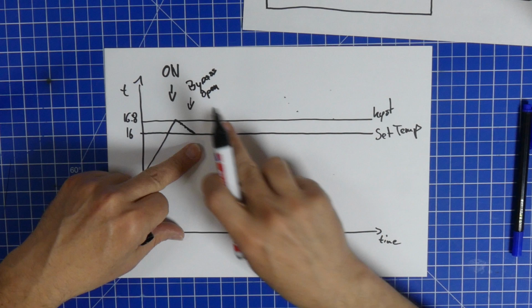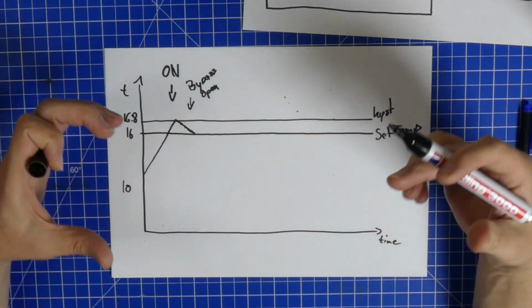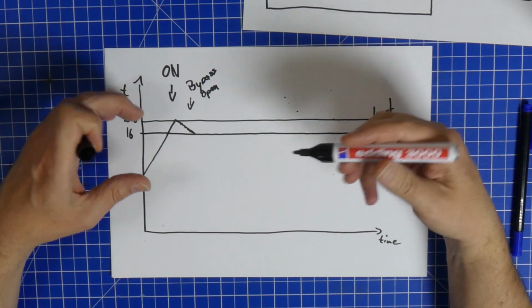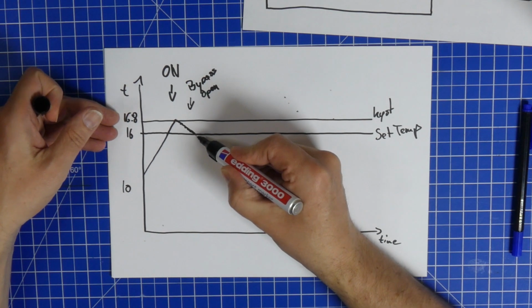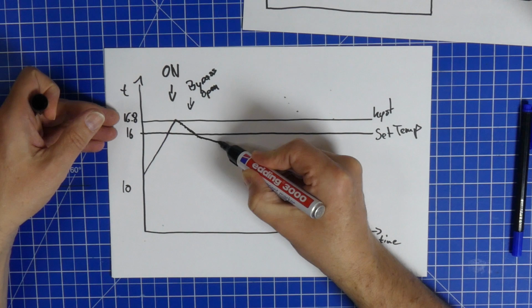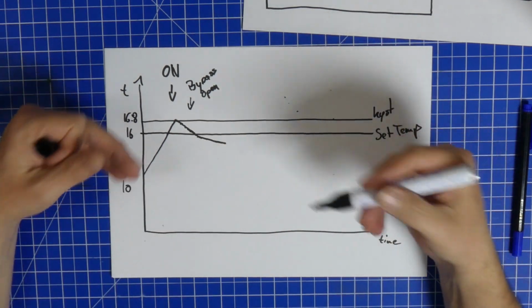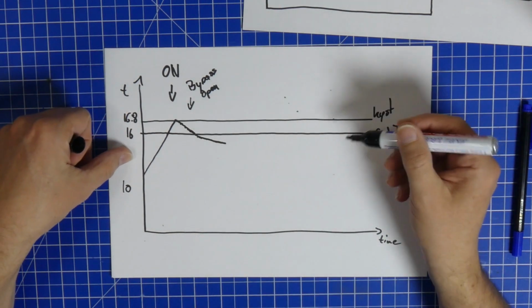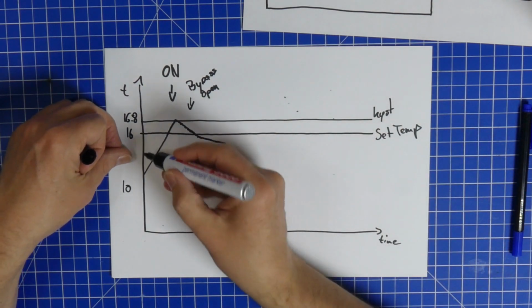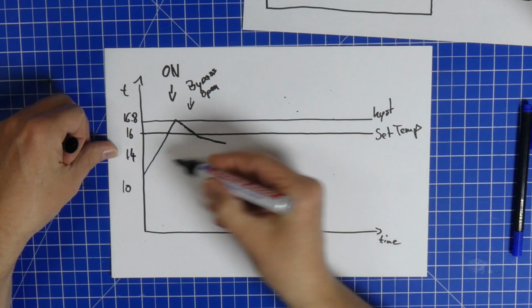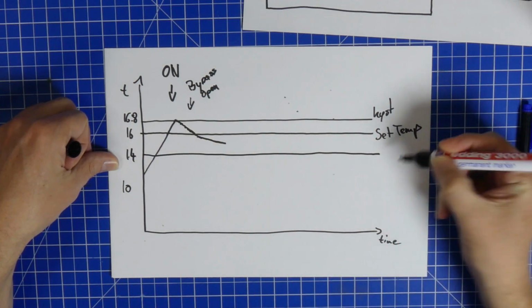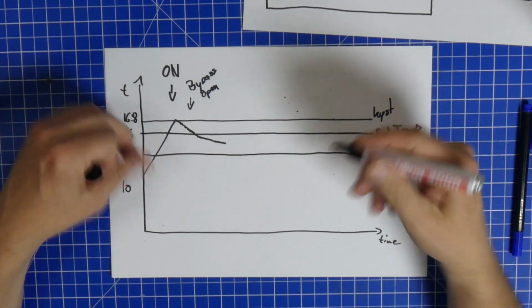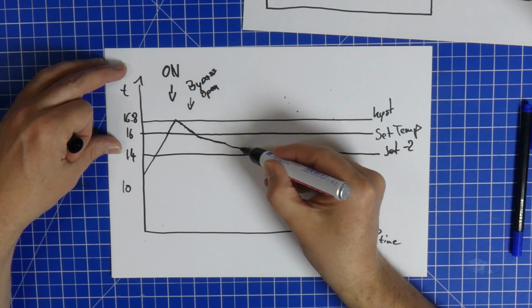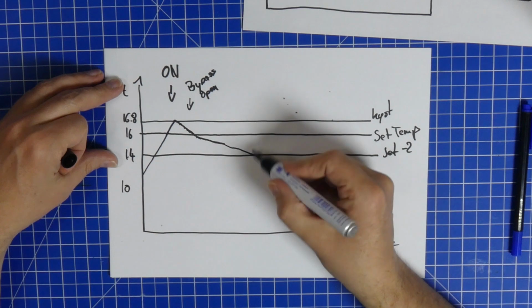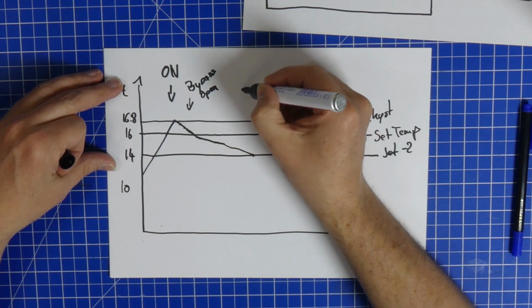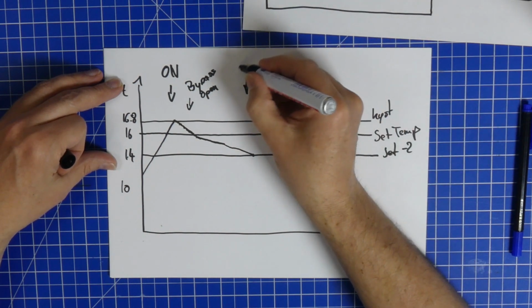And as it opens, the whole AC part of the water chiller becomes a lot less effective. So it keeps on cooling, but just a little. And over time it will cool a little, but not very much. Now there's a second set point, which is set inside the machine, and that is our set temp -2, and that is 14 degrees in this case. And if we put this in here, which is our set -2, and this is hard configured in the controller, the temperature will go down here, and it will just stop. At that point, right here, the whole chiller AC is going to turn off.